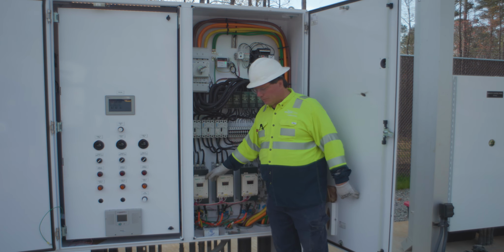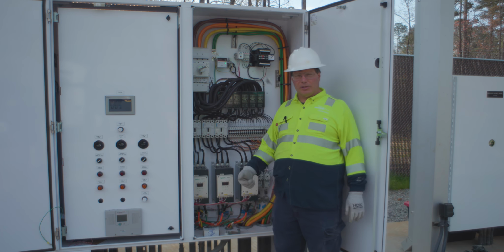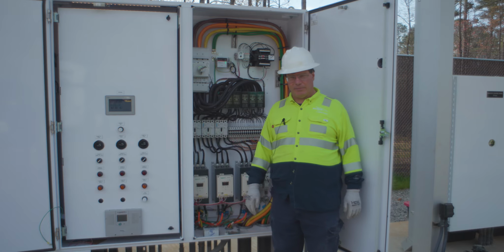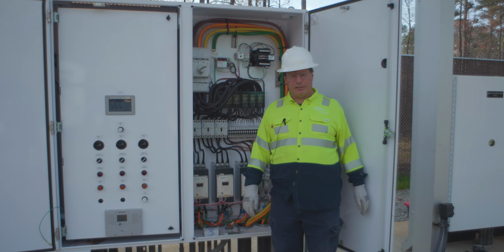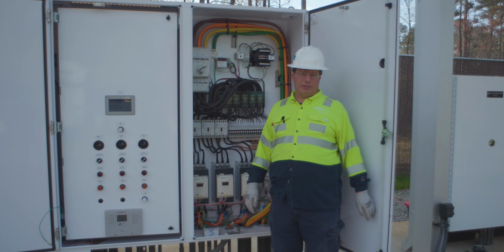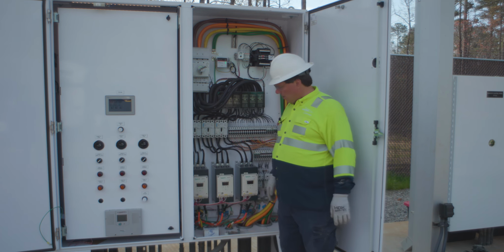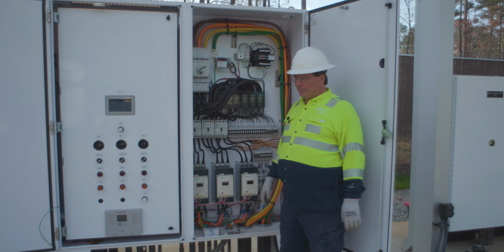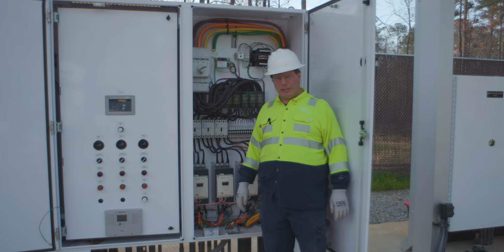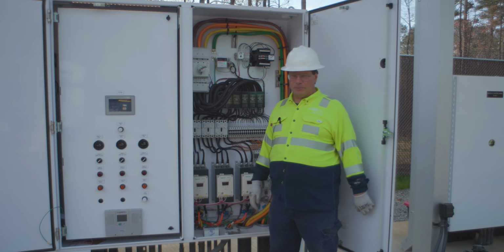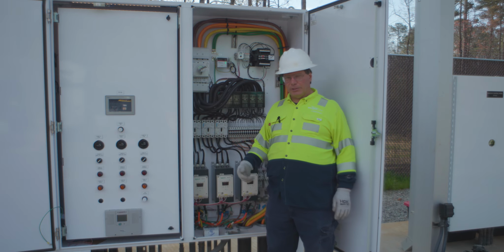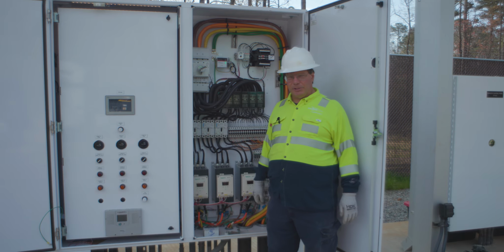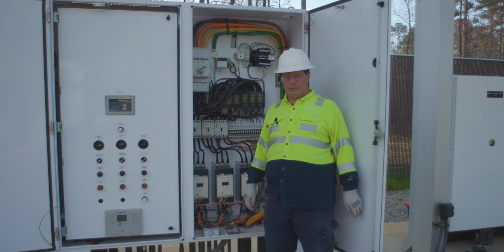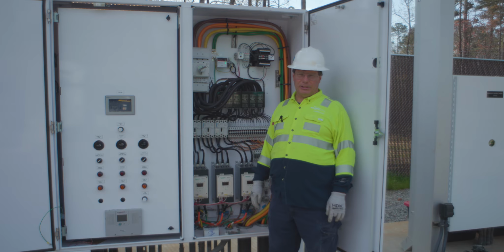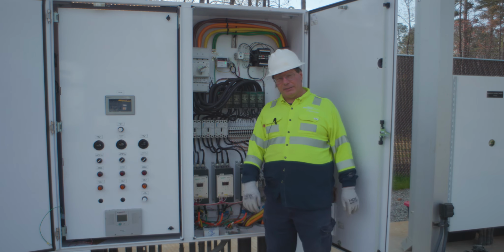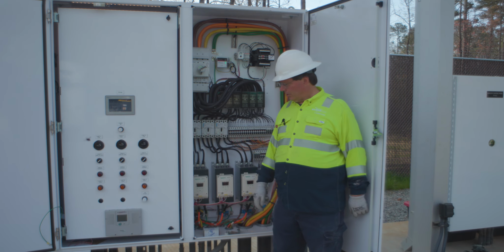Then you have reduced voltage soft starts, which slowly start the pumps. I think they're set for a 10-second ramp and a 10-second ramp down after they turn off. They're all set for 125 full load amps and 400% of full load amps for starting. So if it's 125 amps, they should be drawing no more than 500 amps during a startup procedure based on the settings in the ATS-22.